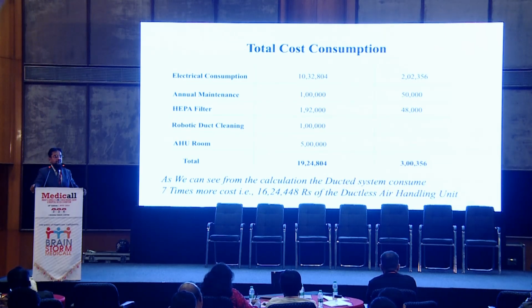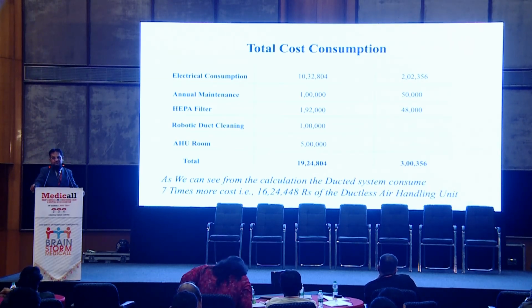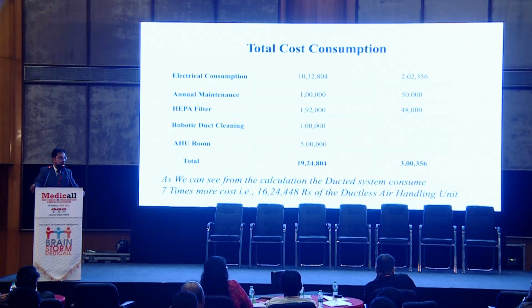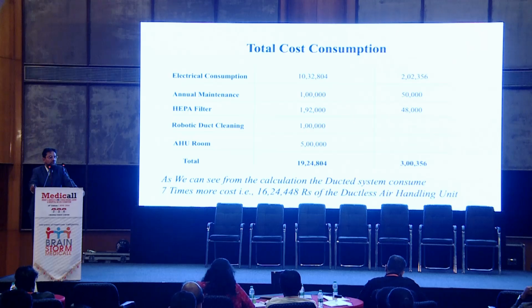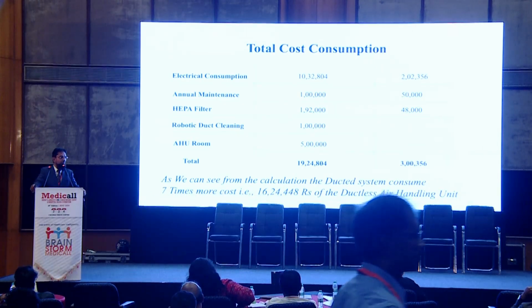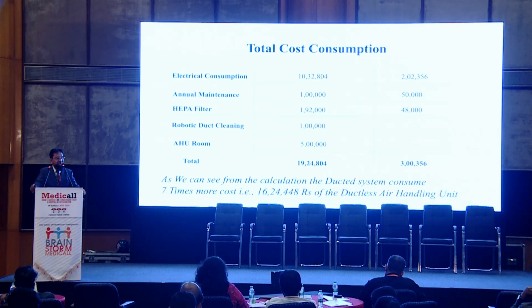Then in the ducted system, whenever you have to change the HEPA, at that time you should do the robotic duct cleaning first. If you don't do the robotic duct cleaning and just change the HEPA, your HEPA will get choked within a week, and whatever money you have spent on changing the HEPA will be of no use. Then keeping the AHU room in your commercial place also has a cost. So these systems save almost 16,24,448 Rs in a year in operative maintenance cost. Is it not a big saving? So this you can save in operative maintenance cost.